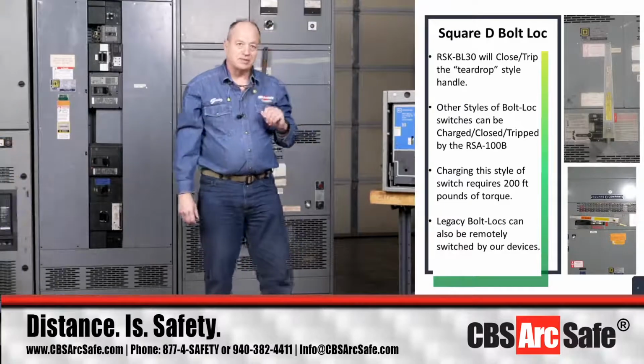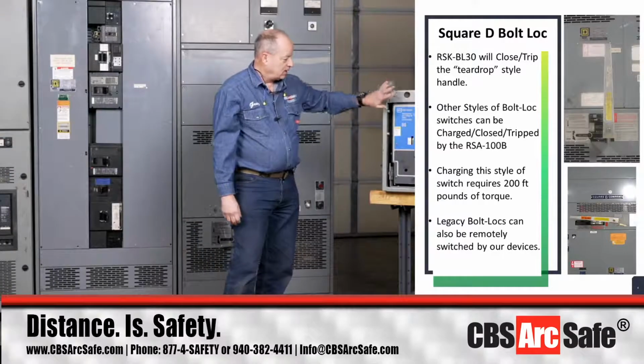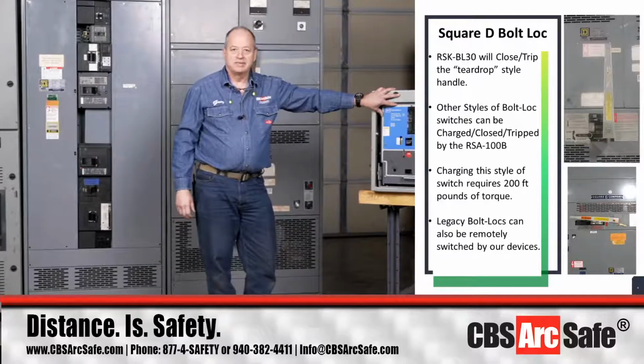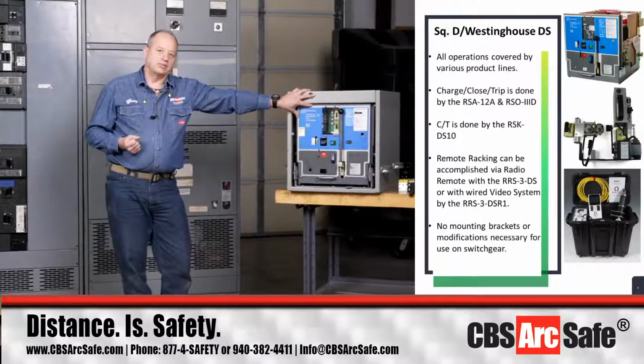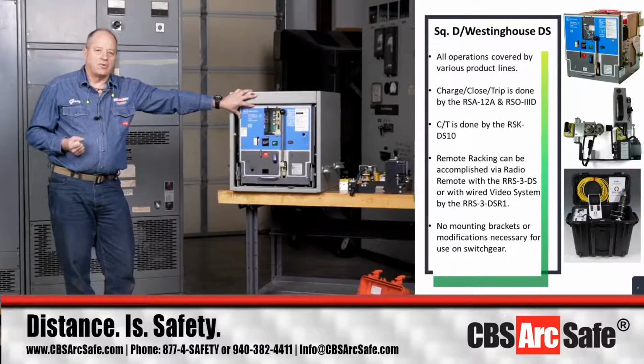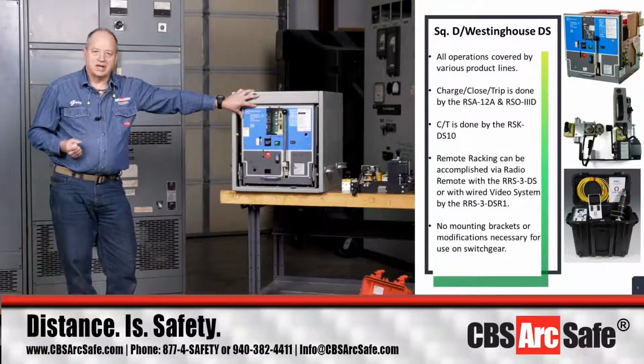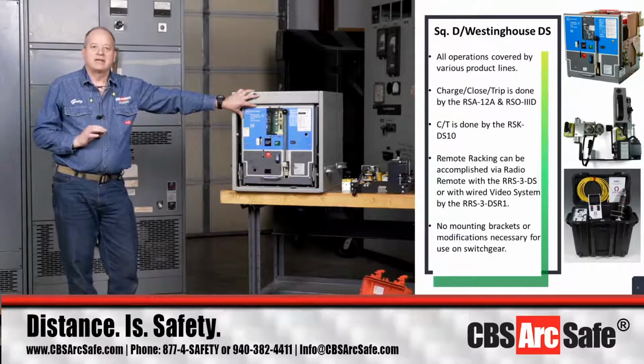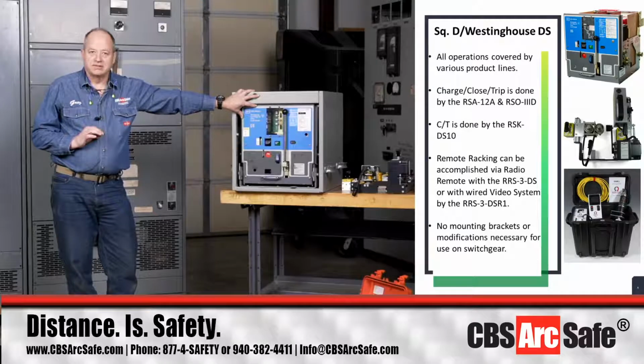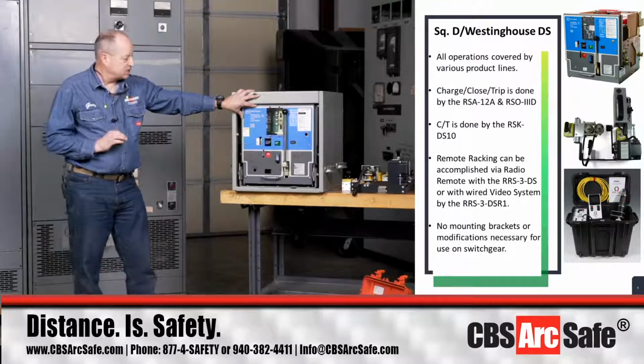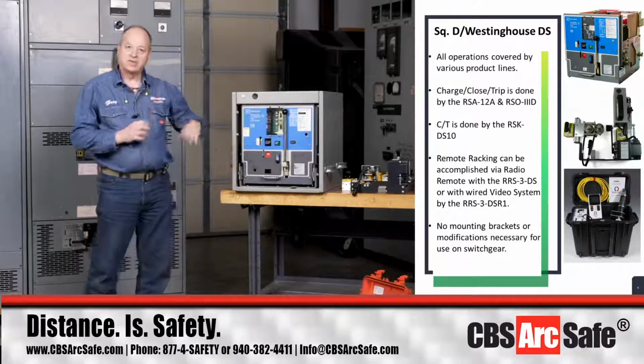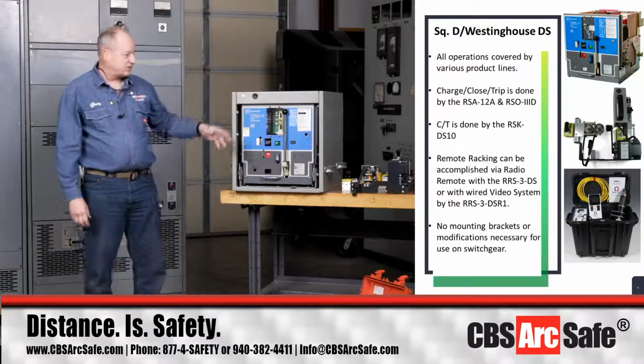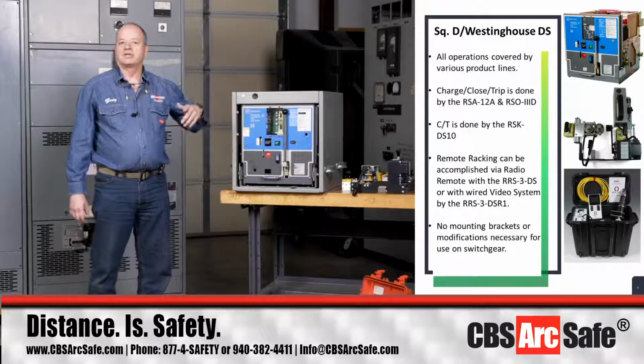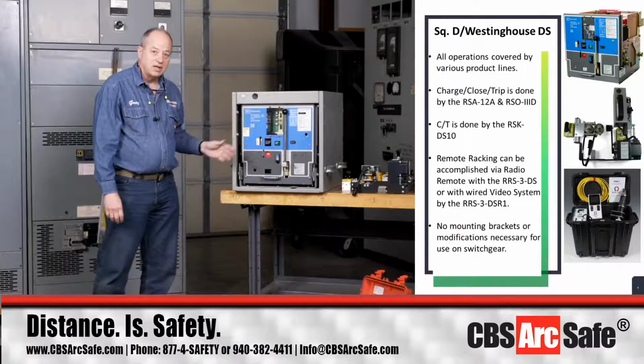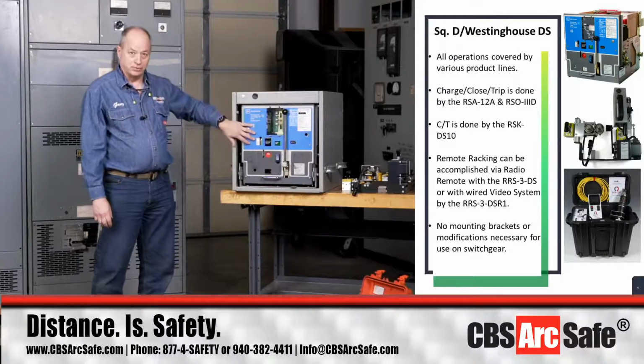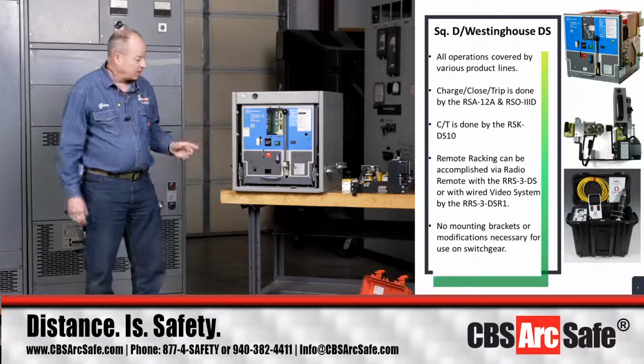Now the next circuit breaker we're going to move on to is the Westinghouse DS. Now you say, Greg, you're talking about Square D products today - for a while, before Square D got the Masterpact breaker, they made the DS breaker under license from Westinghouse. So you'll see these with a plain gray face that says Westinghouse, a red face that says Cutler Hammer, a yellow face that says Square D, and an Eaton face, which is blue. They're still a DS breaker.